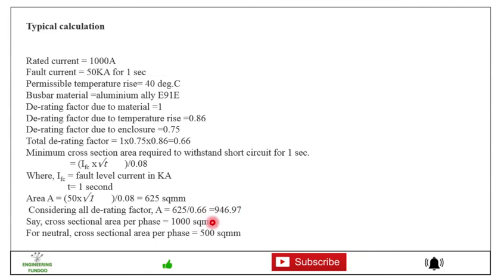So that will be 1000 square mm. For neutral, cross section area per phase will be 500 square mm. So this is how it is calculated. So there are a number of ways by which you can calculate the busbar sizes. One is thumb rule, then you can also apply a formula, then you can calculate temperature rise also. There are a number of derating factors also available as per the standard, and that also you can consider for calculating this size.